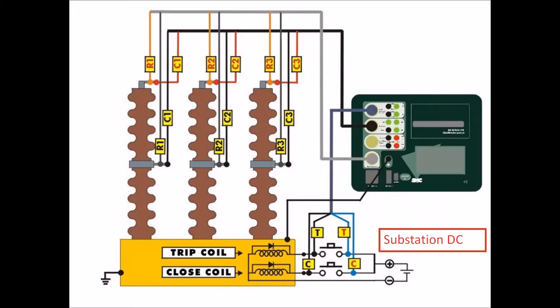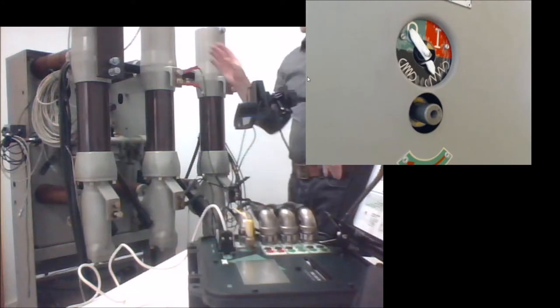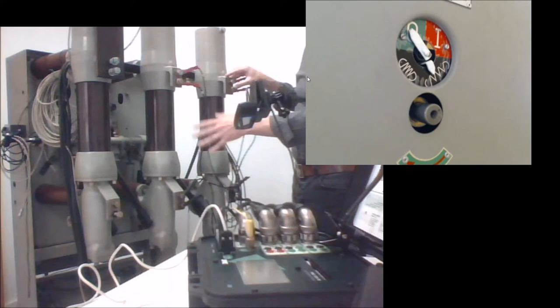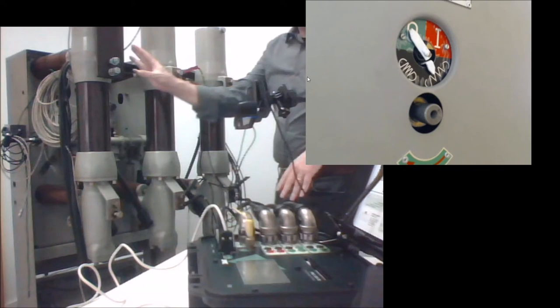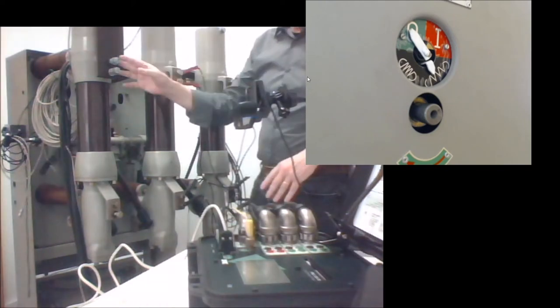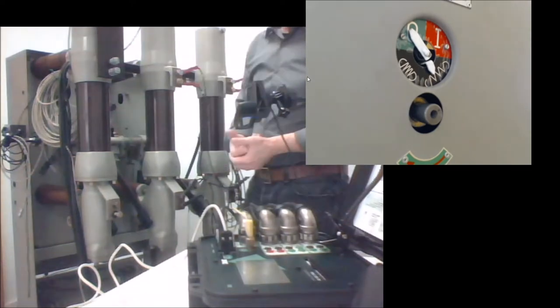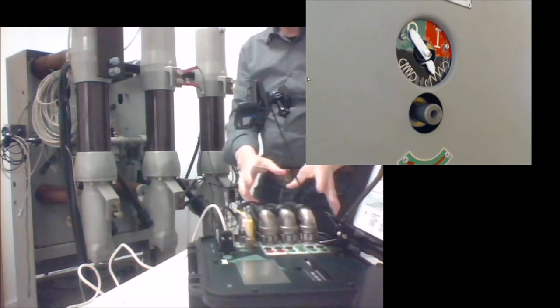I want to describe how the connections to the main contact are made. On the screen we can see a diagram showing the multi-connectors going from the instrument. The first multi-connector goes to the coil control in the breaker. The second one goes to the main contacts. And the last one also goes to the main contacts for contact resistance measurement.